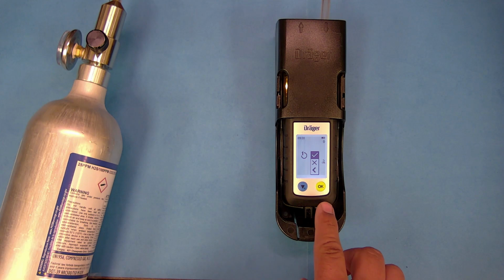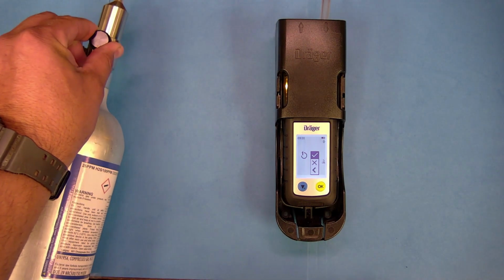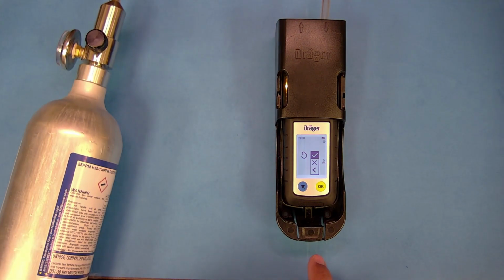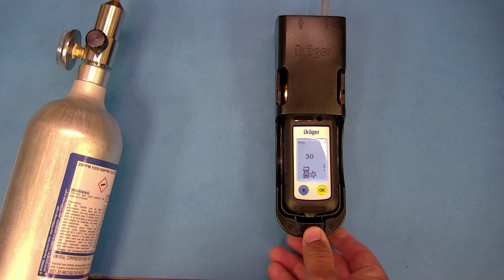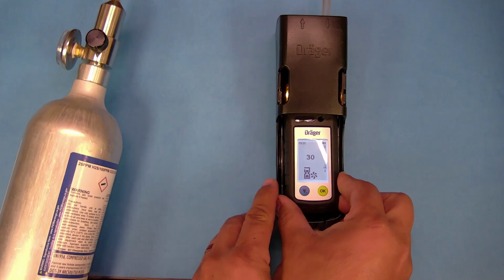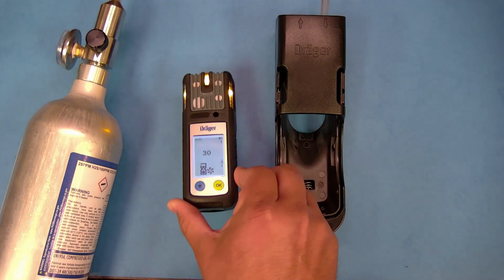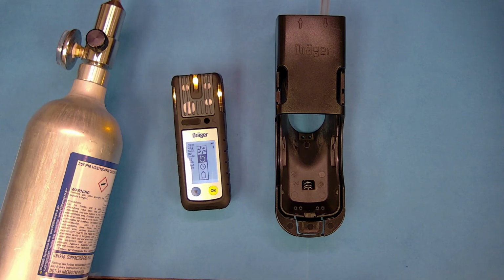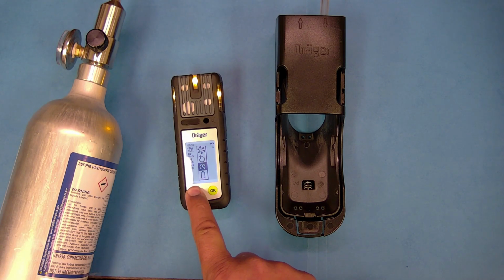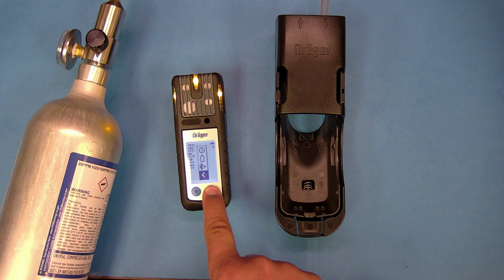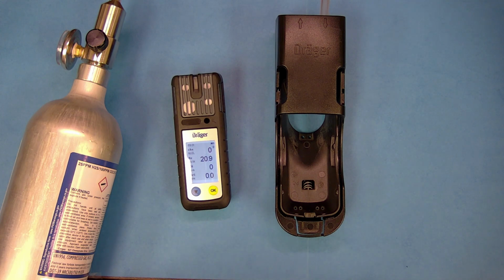You'll want to stop the flow of gas at this point, and once the check mark is highlighted, you can press OK again to successfully record a calibration. From this menu, you will have to press the blue button until you get back to the back arrow to exit the menu and go back to normal operating. Press OK, and you'll be back at your normal operating screen.